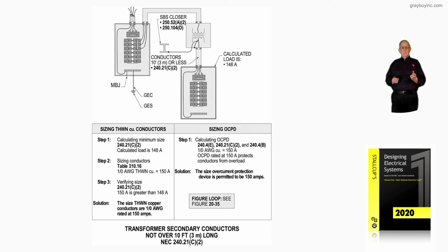And then notice your 150 amp overcurrent device protects the conductors in accordance with 240.4 that we've looked at previously. It protects the equipment in accordance with 240.3. It also protects your conductors. So this installation and the calculations you see will fully comply with an industrial installation of secondary conductors.